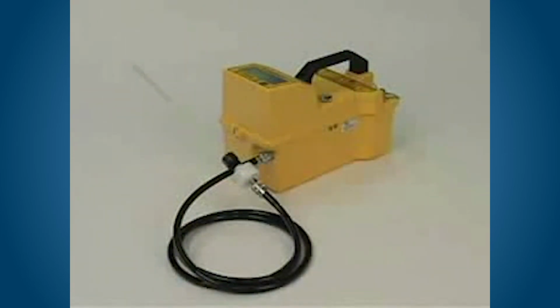The Eagle sample drawing system is designed to provide a continuous flow of sampled air to the sensors for long periods of time while keeping out liquids and dust. With proper setup, this system can draw a sample from up to 125 feet away from the Eagle at a rate of 1 second per foot.